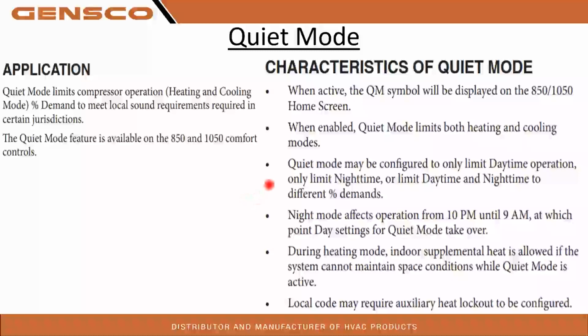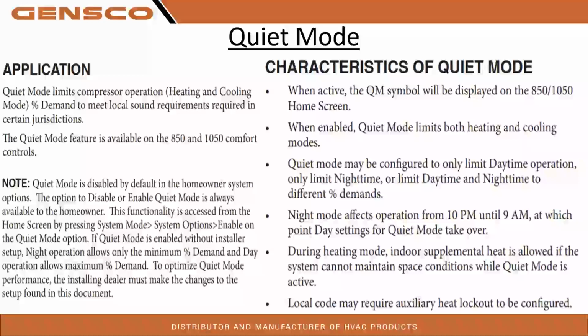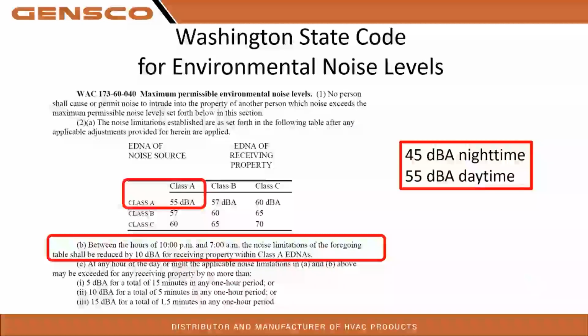But with our variable speed, we can access quiet mode and actually cut that compressor demand at night. That's where that nighttime setback comes in. So the compressor is not as noisy and it meets the sound requirements. So keep that in mind. We can do a lot with that. And here's our Washington State code at this time. That's pretty low.